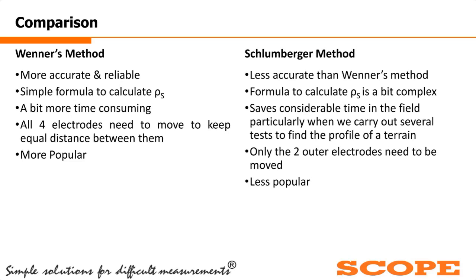So this is the comparison between Wenner's and Schlumberger's method. Wenner's method is more accurate and reliable as compared to the Schlumberger method. Also, the simplified formula to calculate the resistivity is a simple calculation as compared to the Schlumberger method, but it is a little bit more time consuming, as the distance between the electrodes is very high, lots of field work is required, and it is time consuming. Then it is widely used as compared to the Schlumberger method, due to its simplified formula and more reliable accuracy.